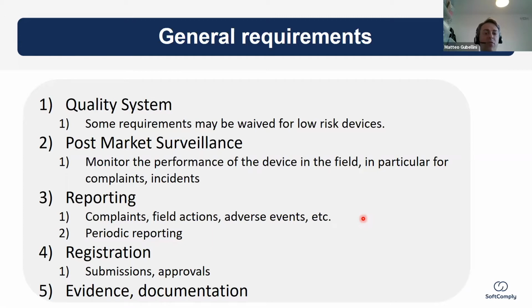And of course, you have a requirement to register the device, which typically is defined in the law as the requirement for the submission of the approval and how you receive an approval from the local authority and what are the conditions under which this approval is still valid. And of course, there are general requirements of evidence and documentation that are required to demonstrate compliance to all the other points.